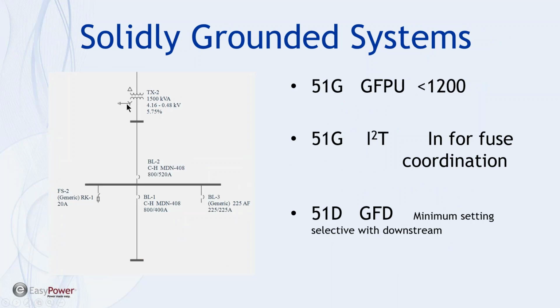Because in the solid ground, where we have basically any ground, line to ground is of concern. We have integrated fault protection in our breakers, in our low voltage power circuit breakers and our molded case circuit breakers. So the 51D, or the ground fault detection in the downstream breakers, is the minimum setting that we need to set so it can be selectively set with anything downstream. So the coordination, you want the remote breakers to trip first, and then the breakers farther upstream to trip secondly.